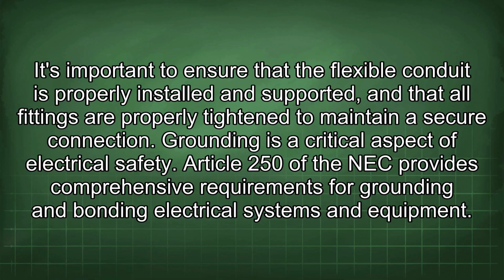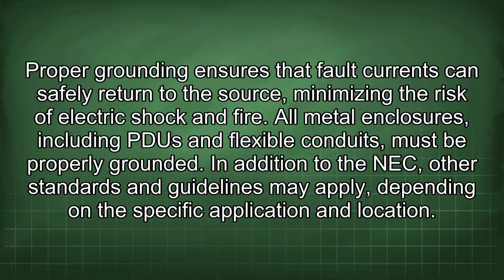Grounding is a critical aspect of electrical safety. Article 250 of the NEC provides comprehensive requirements for grounding and bonding electrical systems and equipment. Proper grounding ensures that fault currents can safely return to the source, minimizing the risk of electric shock and fire. All metal enclosures, including PDU and flexible conduits, must be properly grounded.